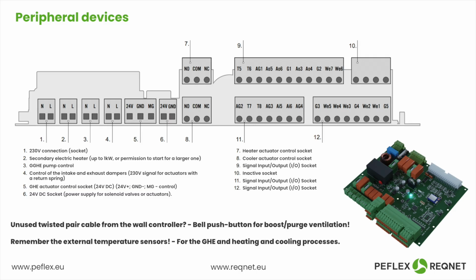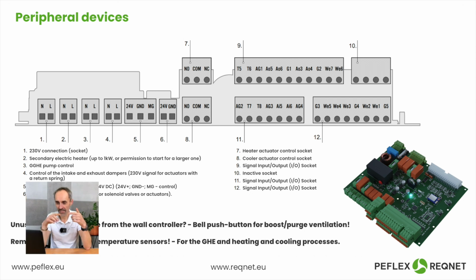Peripheral devices that we can connect to the control automation board. So here we have a whole set of available sockets. So starting even with this ordinary bell switch, which we can use for additional ventilation, and here we have a whole list, so control of the ground heat exchanger, control of the secondary heater, control of the heater, control of the secondary cooler, right? Or the possibility of using signal sockets, or connections to alarm system circuits, or to the fire protection system. So here as well, I encourage you to check the installation and operation manual, where all these functions are described, how we can use them, what we can use, and what else we can additionally connect to the ventilation unit.